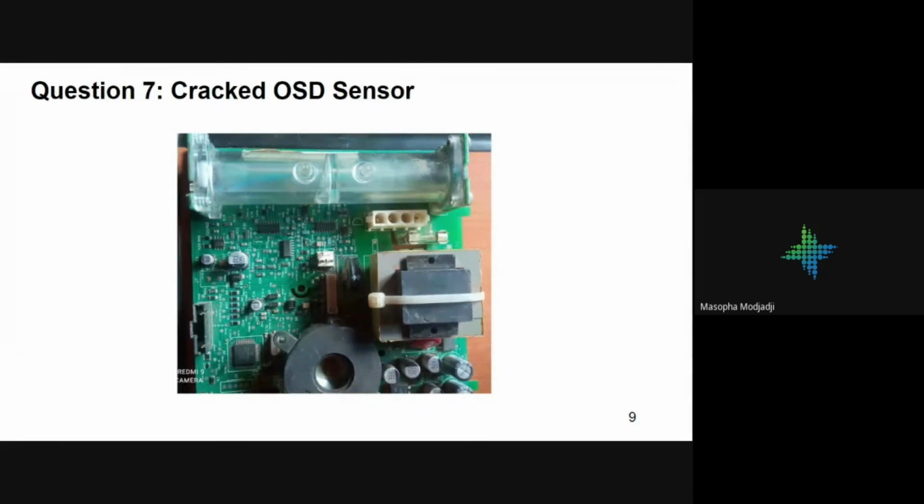The cracks normally develop when you are removing the pipes from the sensor. Sometimes the pipes get stuck. In the process where you force them out, the sensor develops some cracks.